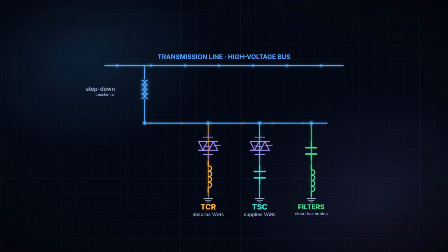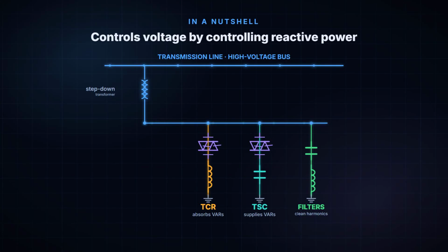A static VAR compensator controls voltage by controlling reactive power with no moving parts. The Thyristor-controlled reactor absorbs reactive power smoothly. The Thyristor switch capacitor supplies it in steps. The filters clean up the harmonics and lend a hand with VARs. And a fast control loop ties it all together, holding the voltage right where we want it. Not bad for a box full of capacitors, coils, and clever switching.